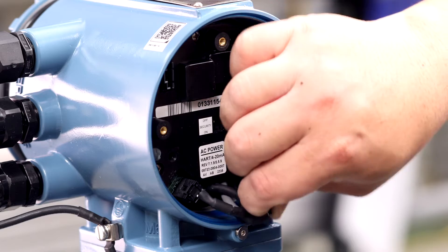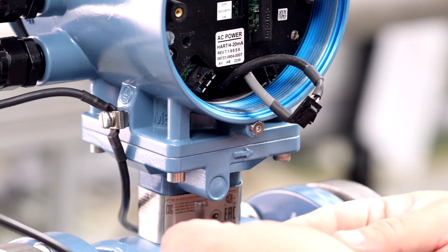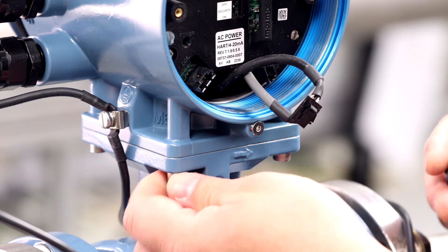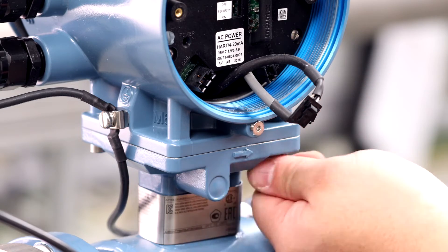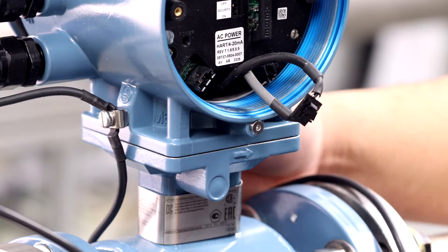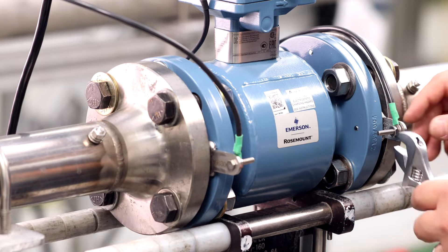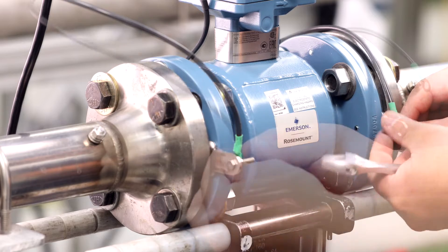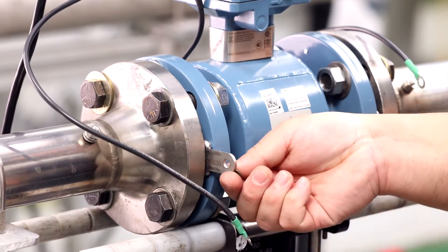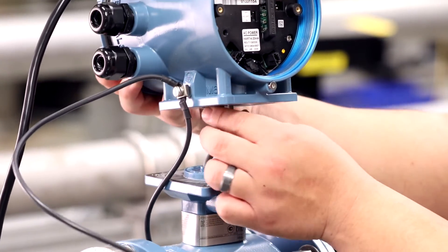Disconnect the coil and electrode cables from the electronics. Next, loosen and remove the four mounting screws using an M5 hex wrench that secure the transmitter to the sensor. Next, disconnect any of the grounding straps from the transmitter. Lift the transmitter away from the sensor while feeding the connection cables through the opening on the bottom of the transmitter.